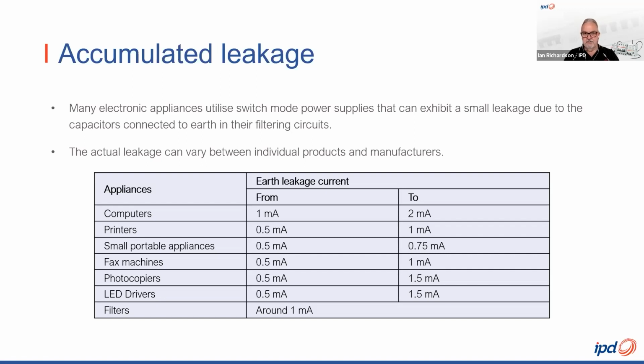It's a challenge. I have to admit, it's a major challenge because a lot of the manufacturers of equipment do not tell you in their tech data what the leakage is. They claim that they comply with a certain standard, but they won't actually tell you. So the table that you can see gives you a little bit of guidance of what it can be. It's not cut and dry. You'll get some products in these categories which are better, and some which are worse. It'll vary a lot. But our message to you is, if you're having issues, have a look at this, because it could well be the issue that you've got.